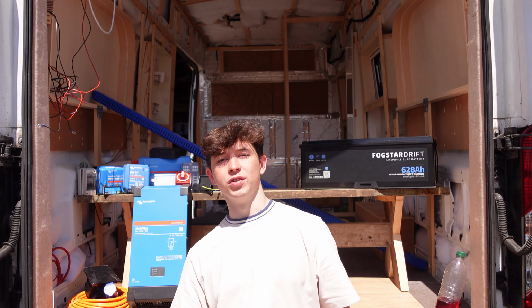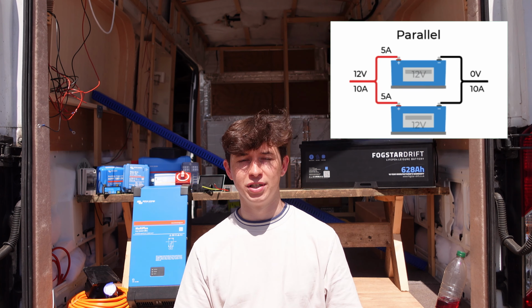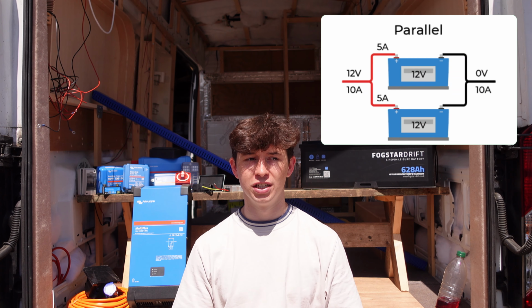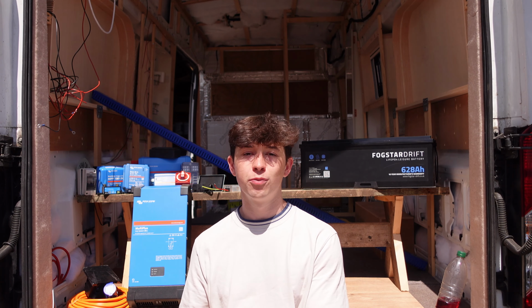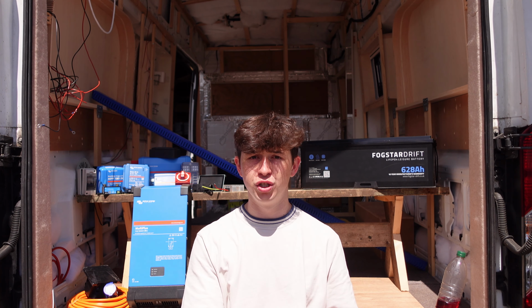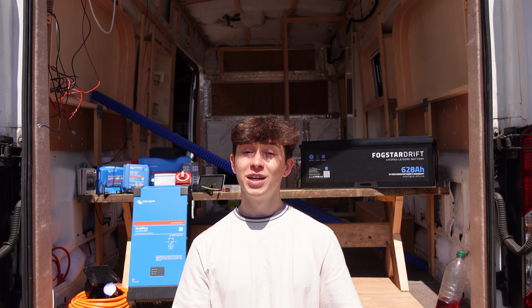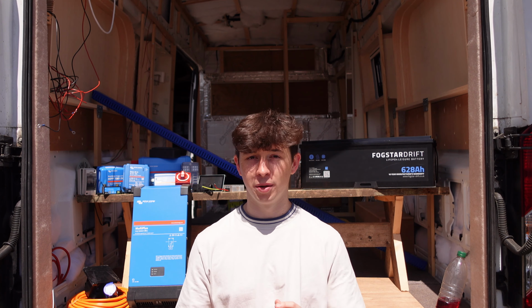So in the case of a 12-volt system, you could have two 12-volt batteries in parallel, essentially just doubling the battery capacity that you have. Or for a 24-volt system, you could have two 24-volt batteries in parallel, which is generally favourable to going with two 12-volt batteries wired in series. As 24-volt batteries are becoming more common, there are a lot more dedicated 24-volt batteries on the market. Because 24-volt systems are usually higher power with larger inverters, the batteries start at a higher threshold, so I think the smallest one that Fogstar offers is a 24-volt 230 amp.